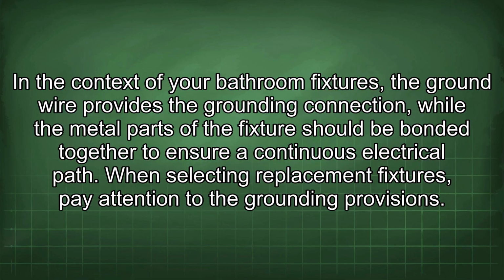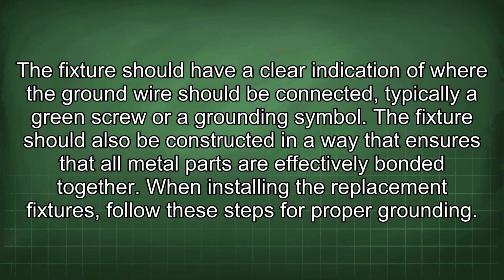When selecting replacement fixtures, pay attention to the grounding provisions. The fixture should have a clear indication of where the ground wire should be connected, typically a green screw or a grounding symbol. The fixture should also be constructed in a way that ensures that all metal parts are effectively bonded together. When installing the replacement fixtures, follow these steps for proper grounding.